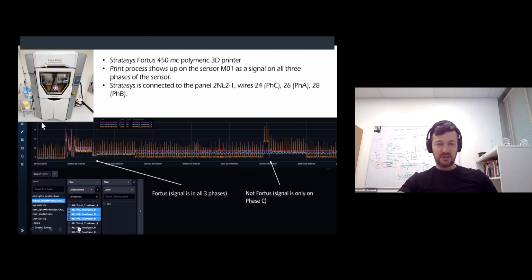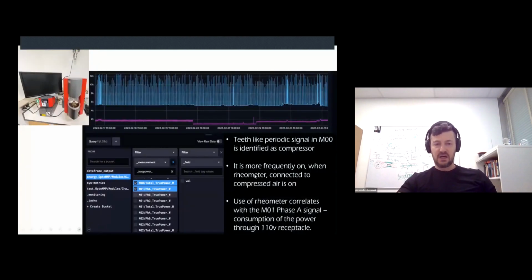For instance, this is a 3D printer, production grade 3D printer, Fortus 450 MC made by Stratasys. We can see that it's connected to 3 phases. This is power consumption of Fortus, while on the same detector you can see a kind of similar shape, but it's only on 1 phase. We have to identify a signal from the printer. We have to monitor all 3 phases of a particular detector and see signal in all 3 phases. Then we know that it's related to Fortus. But if we see signal only in 1 phase, that's something else, which we don't really know. So it's kind of an investigation every time to detect.